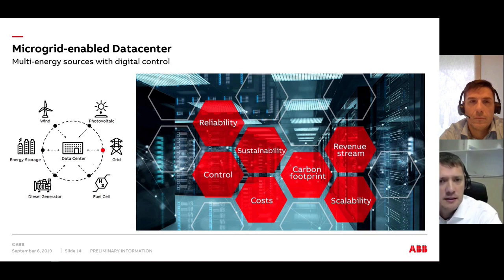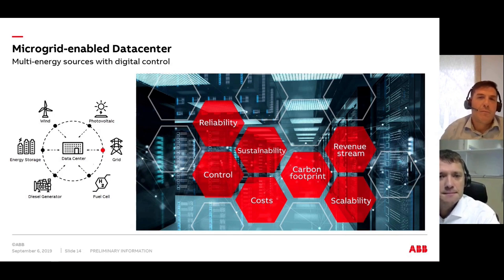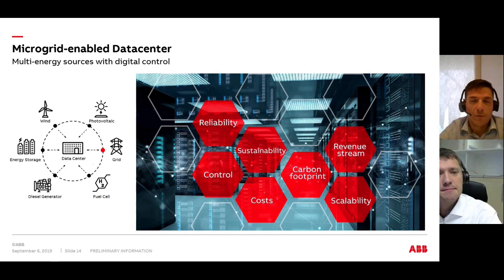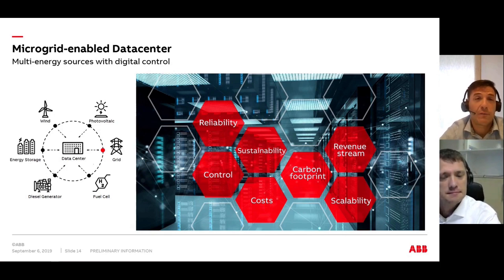Carlos, what can you tell regarding reliability? How will battery storage really help here? We need to consider the variability and the intermittent nature of the renewable energy that we can have in a microgrid-enabled data center. So the microgrid-enabled data center architecture requires reliable technologies and, of course, intelligent control to ensure proper power sharing under grid-tied conditions, but also reliable power during islanding operations. So transitions from grid-tied to islanding operations, and vice versa, are critical. And those are initiated automatically. There is no need for an operator to trigger that jump. Of course, if desired, it can be done.